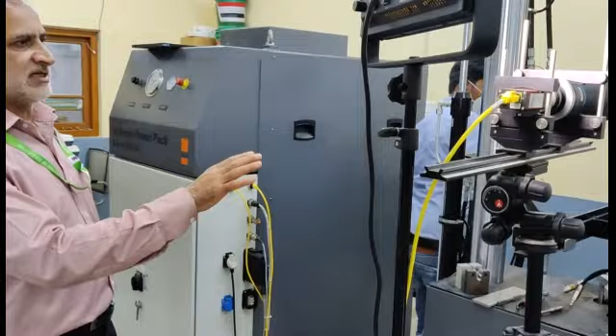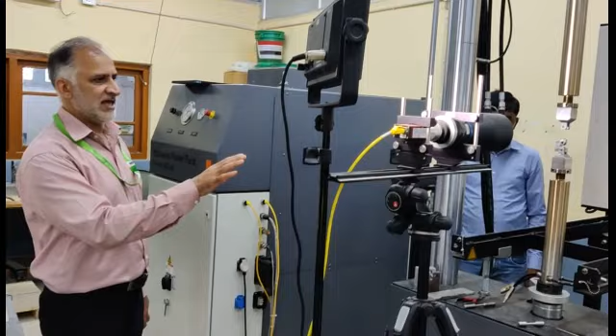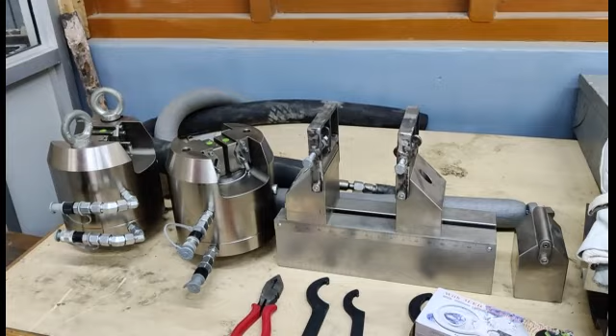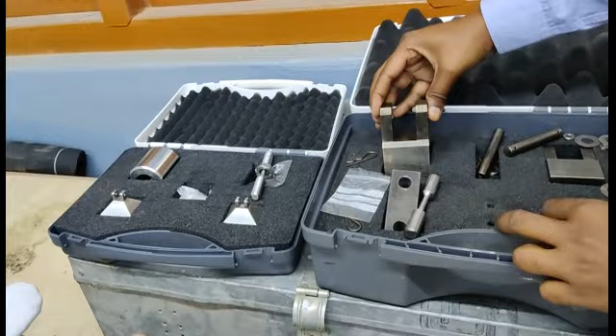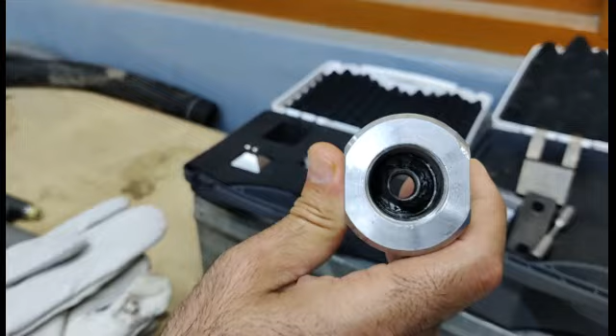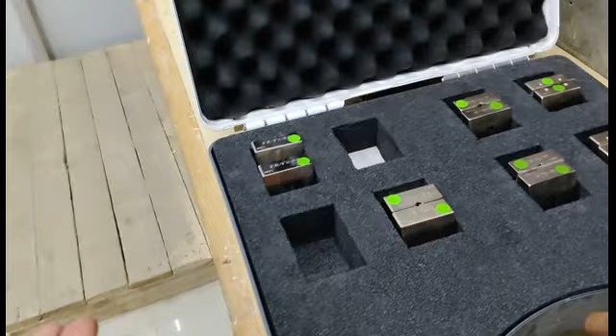It is also possible to perform certain ASTM standard tests like E399 and E647 on this machine. It is equipped with a hydraulic power pack, which has an oil meant for cooling the machine. The oil itself is getting cooled behind this wall by a cooling chamber. These are some of the grips which are available with us for the types of specimens. Those have been already shown, and these are more grips which are available for other types of specimens, and you can see what kind of grips we have.